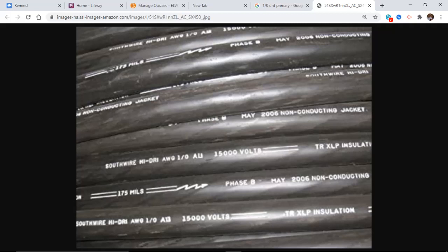Professor V, you could probably chime in on this too. Because of overhead conducting, when you start getting into this, this is a pretty decent sized wire right here. You're going to try to get delivery and reels to match your trailers and whatnot, so you get conductor in increments of miles and dividers of that. Typically on a reel of this kind of conductor, you're going to get half a mile. On overhead conductor, probably a smaller size, you're going to get a mile. Some bigger conductor, you're going to get a quarter mile.